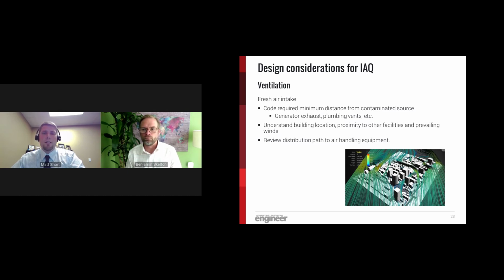A wind study like this is more effective and recommended for outside air intakes on a facility that's being constructed in a congested urban environment. Additionally, we should consider the outside air path to the air handling equipment to ensure that airflow is not restricted and fresh air can be properly supplied to the space.